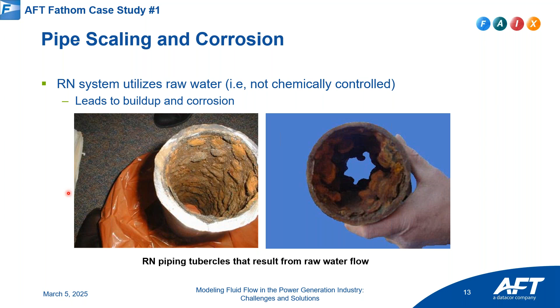So what the utility, Duke Energy, wanted to do is go in and treat the piping to clean it out. But where there was untreated piping that looked like this, they took flow measurements around the cooling water system, and I'll get into this. They wanted to calibrate the model to the in situ piping that looked like this, so that they could actually use the model going forward in the future with piping that looked like this. So what they wanted to do was modify the piping internal diameter because of the scaling buildup.